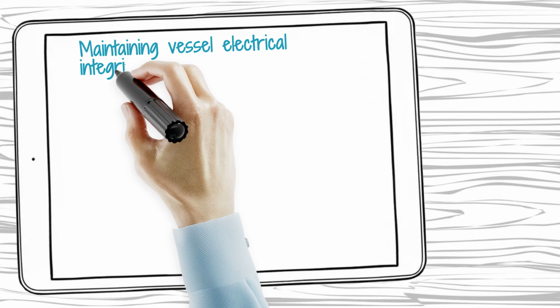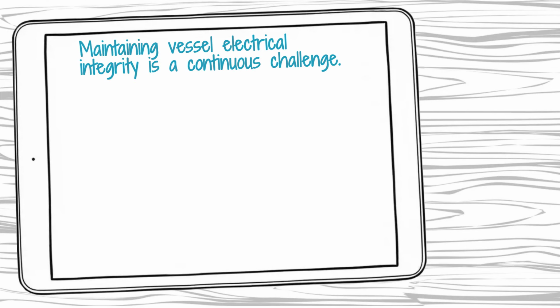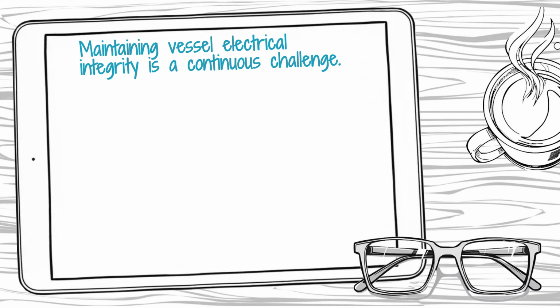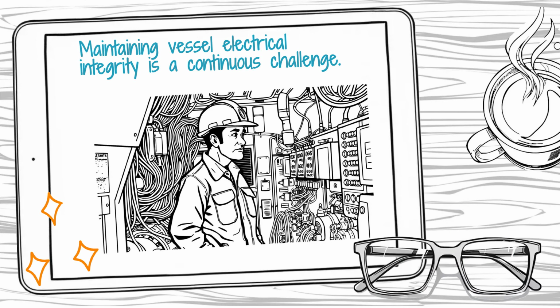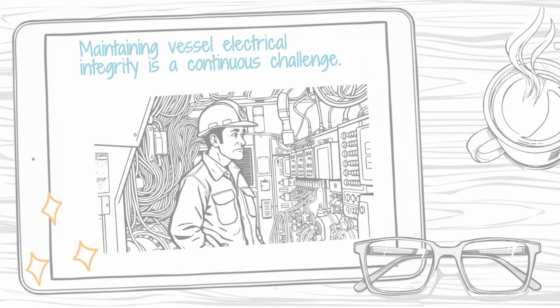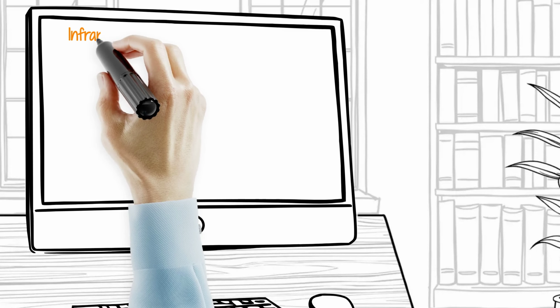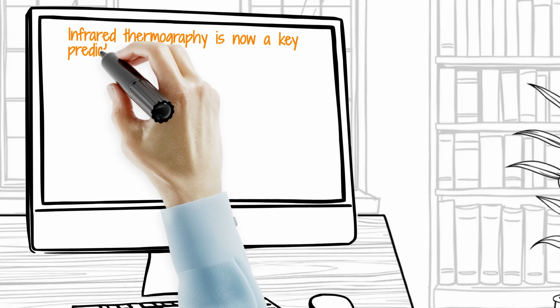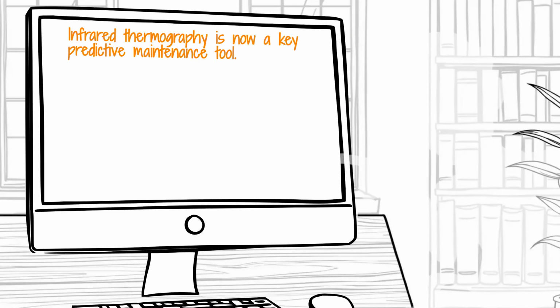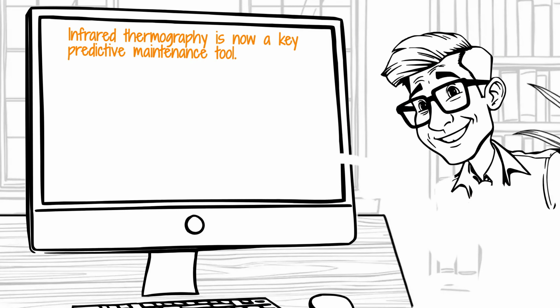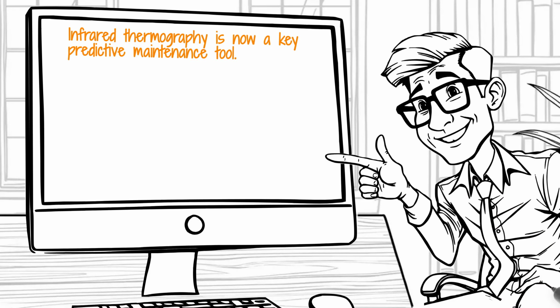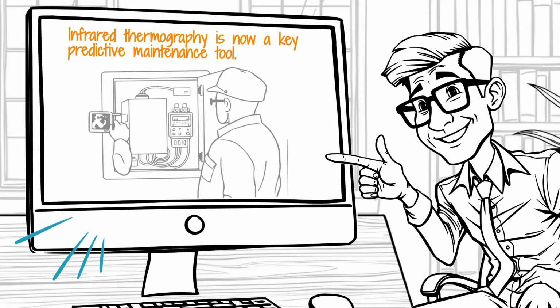Maintaining the electrical integrity of a vessel is a continuous challenge due to the high vibration and humid salt air environments that accelerate the degradation of components. Infrared thermography has become an essential predictive maintenance tool for marine engineers, allowing them to identify potential electrical faults before they lead to catastrophic failure or shipboard fires.